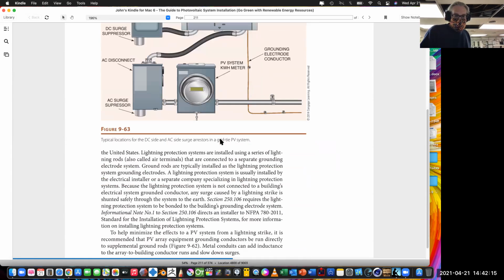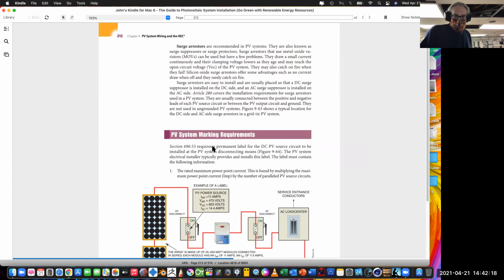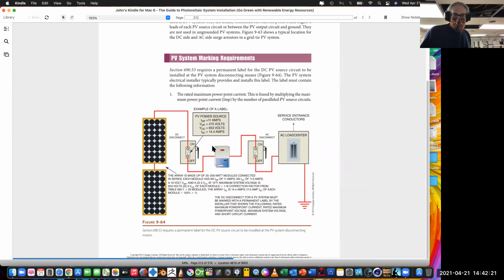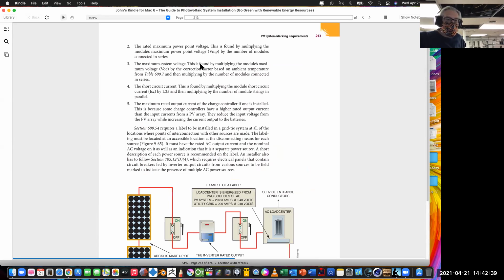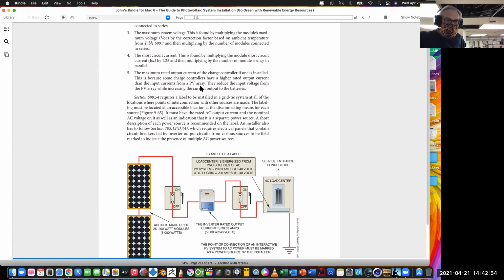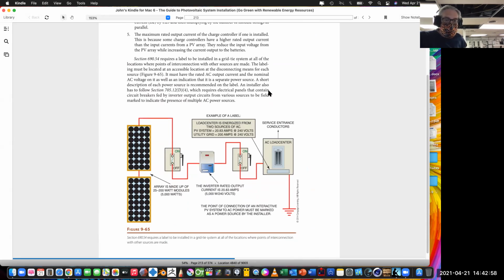Okay, so disconnect, we've already talked about that. We've already talked about marking requirements. Okay, this is something you need to know. This is a lot of stuff I know, but that's why we're still in chapter 9. Section 690.53 requires a permanent label for DC PV source circuits to be installed at the PV disconnect. We know that already. So the rated power point voltage, as we know, is VMP. We know we do calculations for the maximum voltage by multiplying the VOC by the correction factor based on ambient temperature. So they're just reiterating stuff we've already learned here at this point.